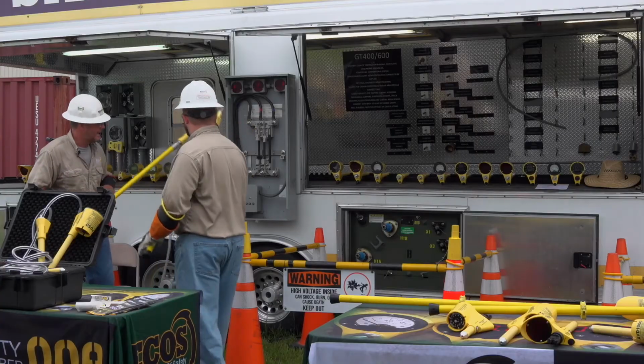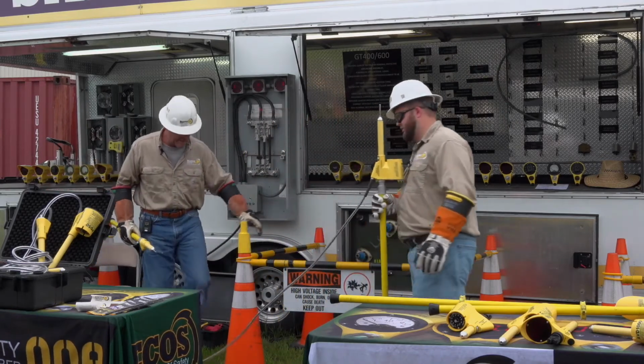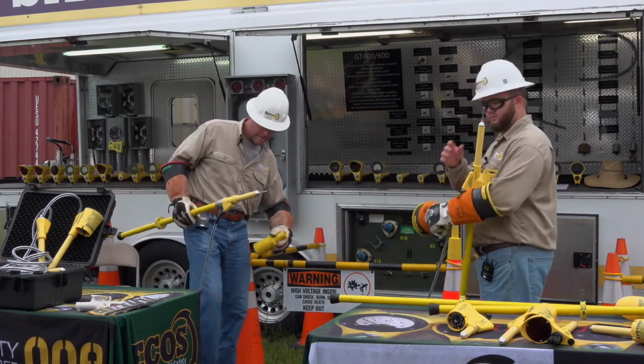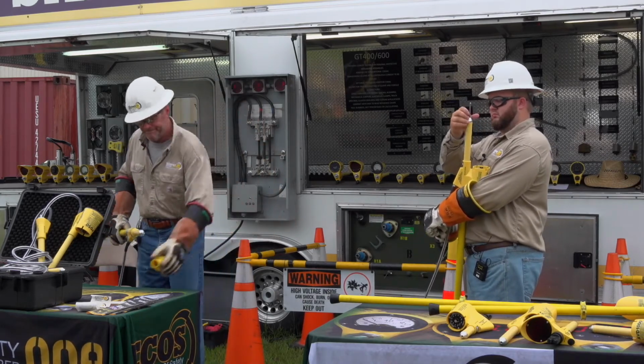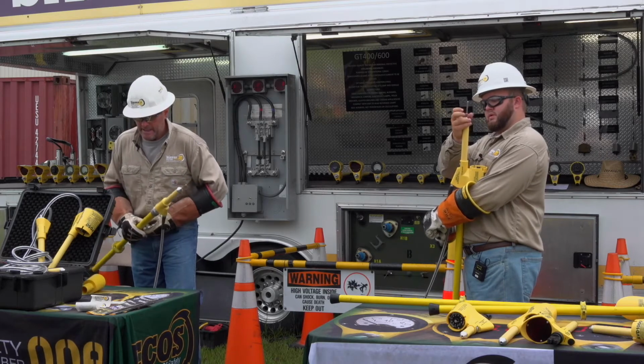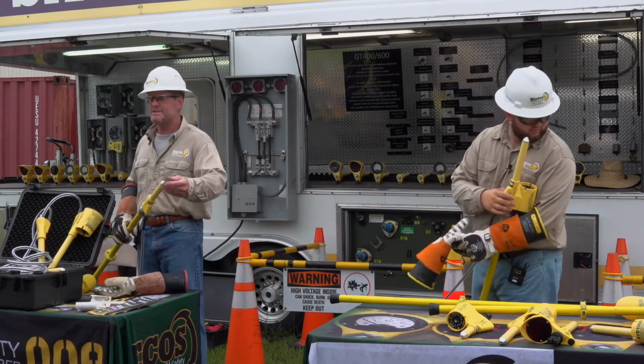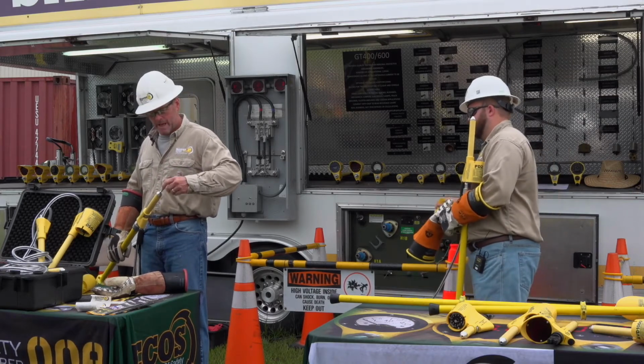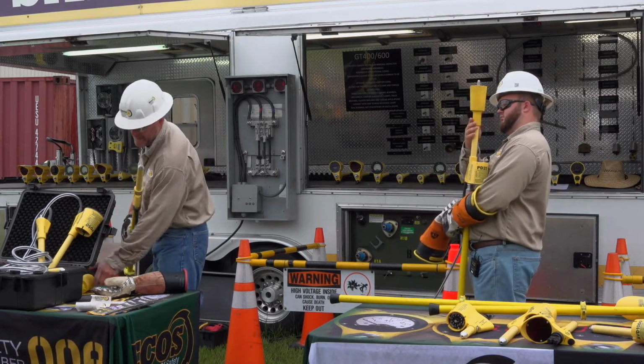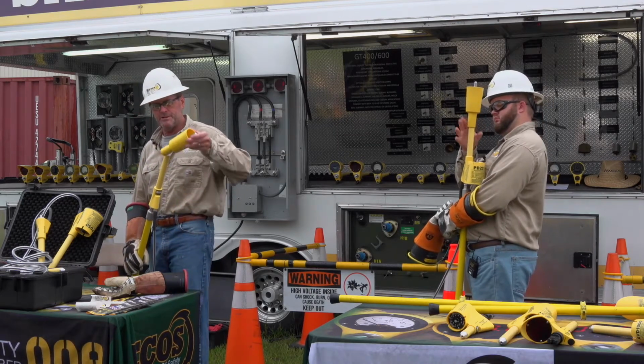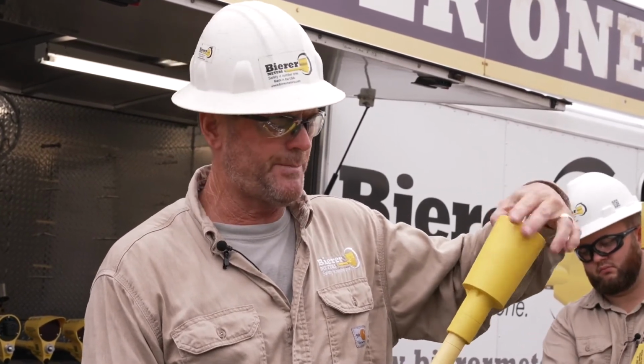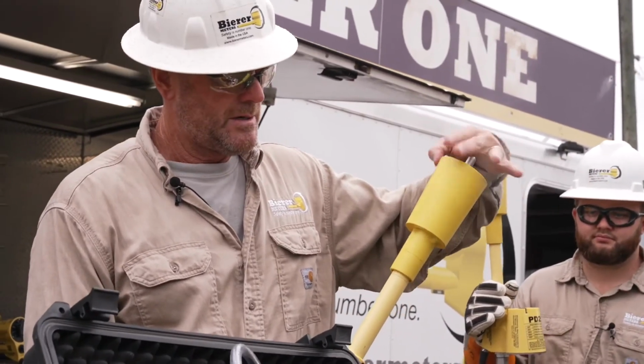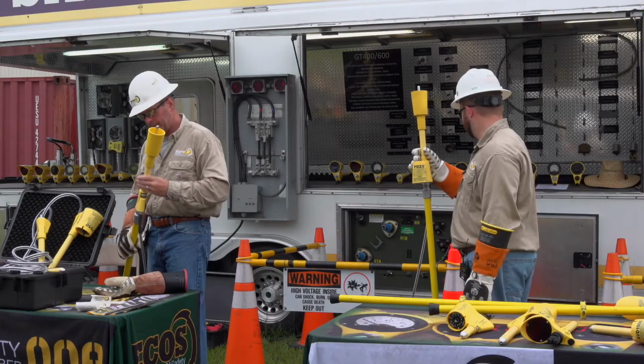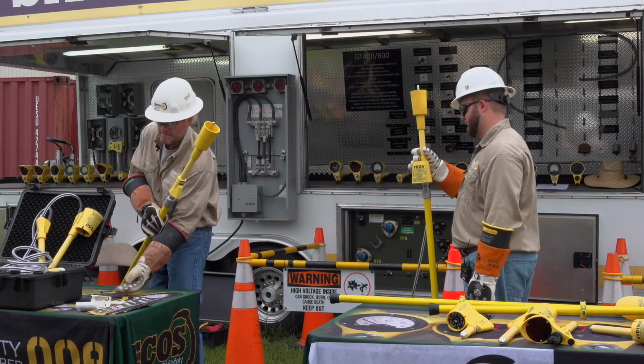Out of phase. Okay? We'll go to the hot bushings right here. We're going to put our bushing adapters on, the proper accessory on our hot bushings. I've had folks say, hey, why can't I just put my straight probe into that hot bushing? And I tell you what, if you want to see an arc flash and have some fun that day, if that's really what you're into, then that straight probe is probably the accessory you want to use, and you need to change up your attitude a little bit. But you've got to use the proper accessory, the bushing adapter, to protect yourself from a potential arc flash, right? Okay, go ahead, Ryan.